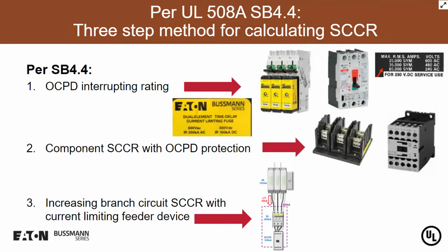In the breaker scenario, we can have 100,000 amp breakers, we can have 10 kA breakers. But in general, whatever the lowest interrupting rating is of that overcurrent protective device, so if we have a 10 kA breaker protecting that control transformer or that power transformer, then the whole panel or machine comes down to 10 kA. So the first step is we want to look at all of our overcurrent protective devices and find the lowest interrupting rating of those devices, and that's what step number 1 is. Now, the panel will not be any higher than that. The SCCR cannot be any higher than the lowest overcurrent protective device interrupting rating.